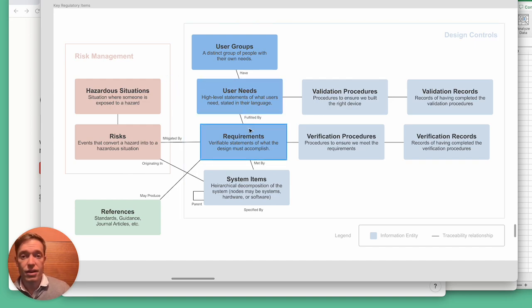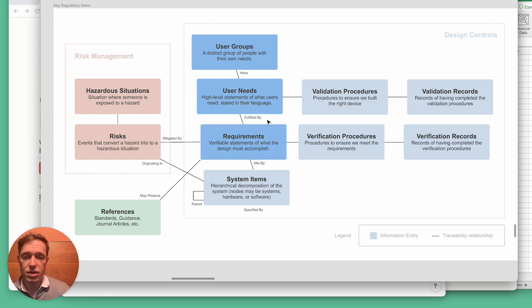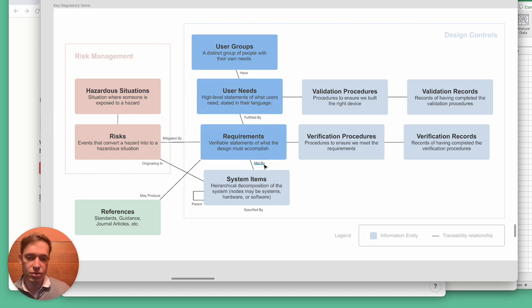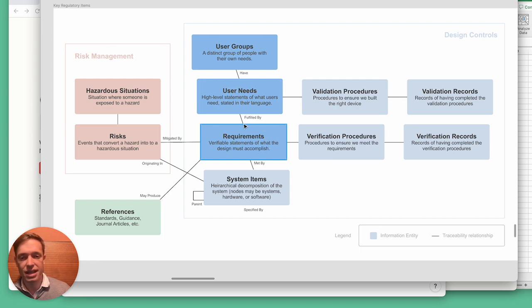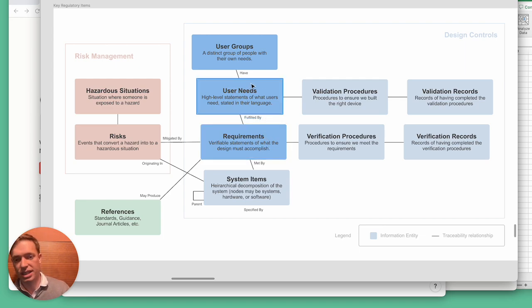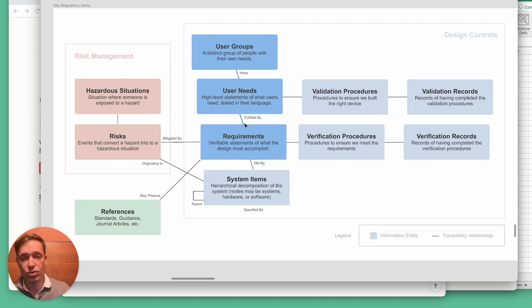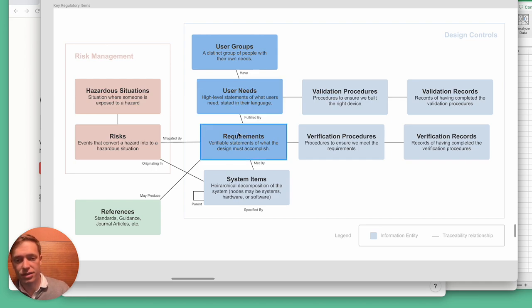If we're following IEC 62304, you may need to have system requirements and software requirements. So the software requirements would then link to the system requirements, which would link to the user needs. And if your tool doesn't support that, it can be difficult to deal with.